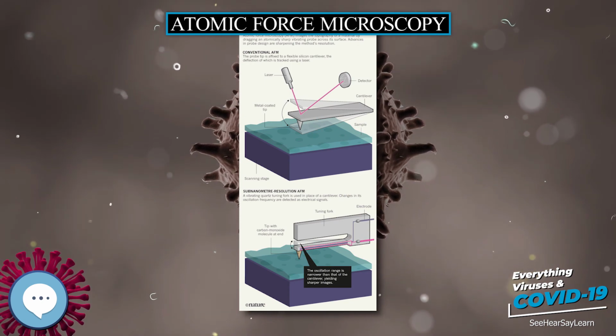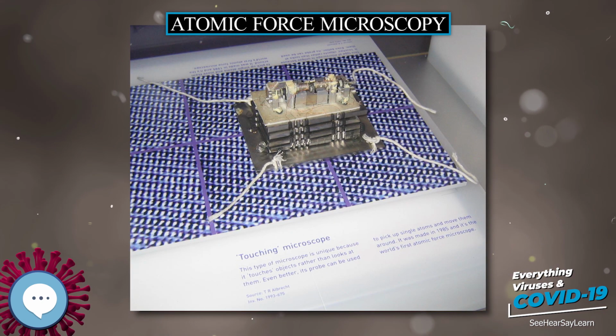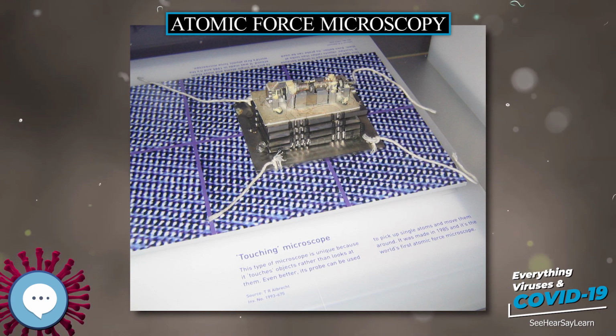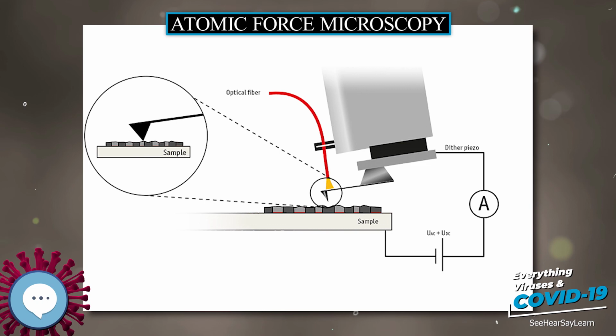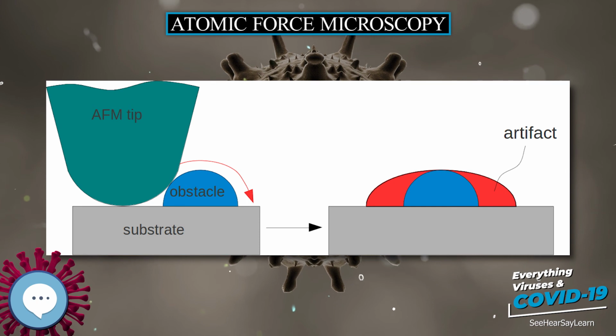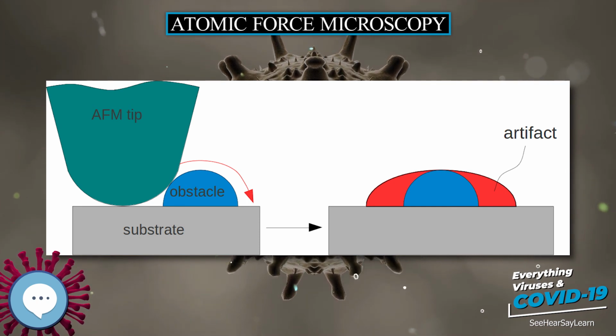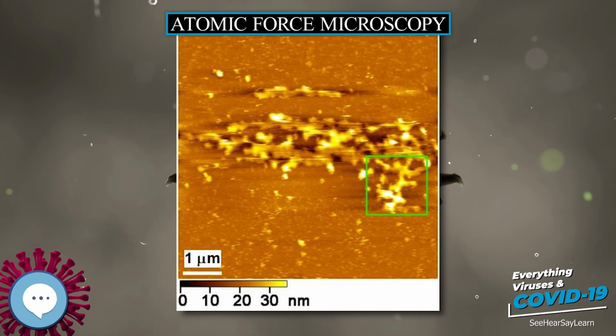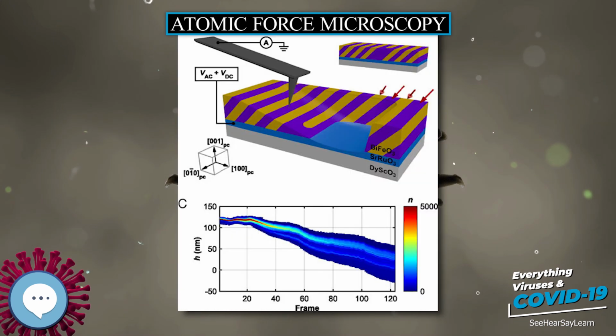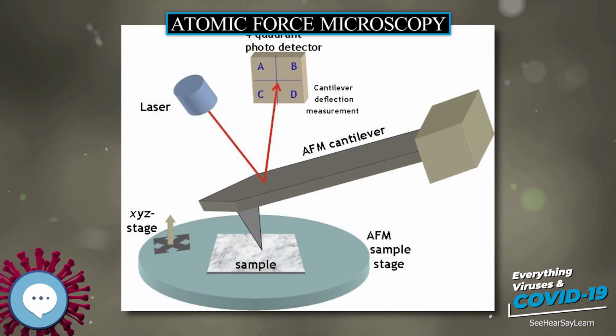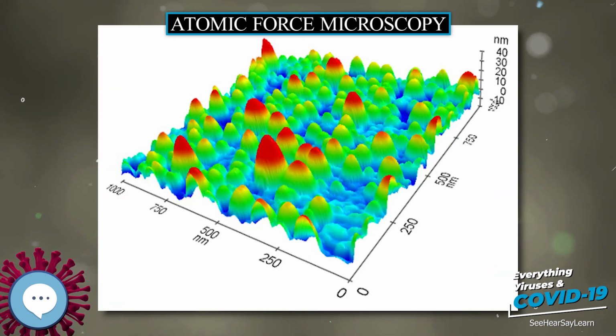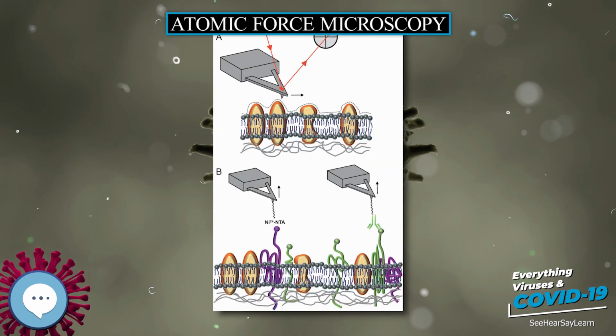In 1986, the same year as the AFM was invented, a new piezoelectric scanner, the tube scanner, was developed for use in STM. Later, tube scanners were incorporated into AFMs. The tube scanner can move the sample in the X, Y, and Z directions using a single tube piezo with a single interior contact and 4 external contacts. An advantage of the tube scanner compared to the original tripod design is better vibrational isolation, resulting from the higher resonant frequency of the single element construction, in combination with a low resonant frequency isolation stage. A disadvantage is that the XY motion can cause unwanted Z motion, resulting in distortion.